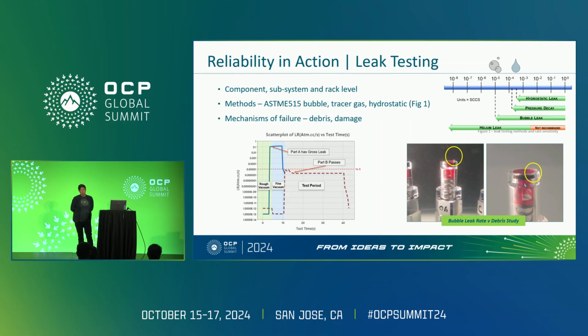Once you've got your cold plate loop, your manifold, your rack level system set up, it's time to run some tests. And for direct liquid cooling, that often comes down to leak testing. The graphic on the upper right is maybe where I'll point your attention. We've overlain some different leak testing methods with essentially the order of magnitude of leak that each can detect. As we go from right to left, you'll see that some of those test methods start to drop off. They can't reliably measure that resolute of a leak rate. The further left we go, we've also got some things going on under the hood that a lot of my colleagues could probably spend a couple hours explaining to you and talking through the nuances of, but we're actually moving through different flow regimes.